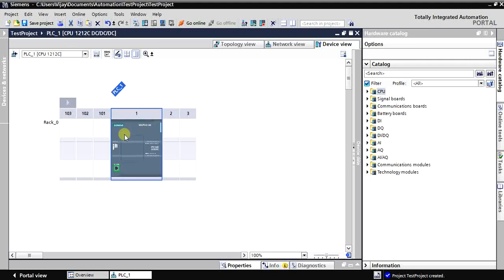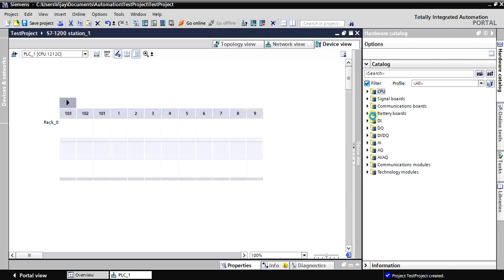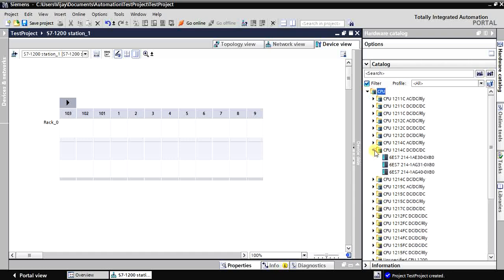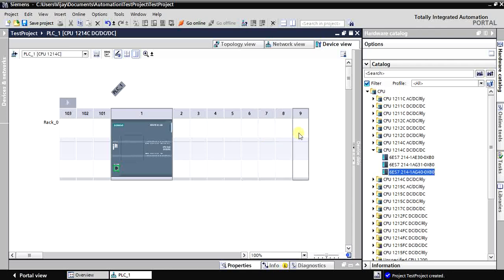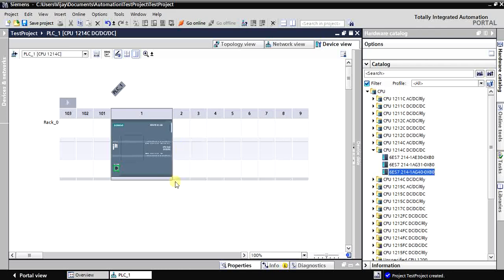If you select the CPU 1214, you get more slots. I'm deleting this one and selecting the 1214 DC/DC/DC by double-clicking it. You can see it goes up to slot 9, meaning you can use slots 2 through 9. If you select the 1212 you only get slots 2 and 3. For the S7-1500, you get slots 0 to 31 — I'll cover that in another video.